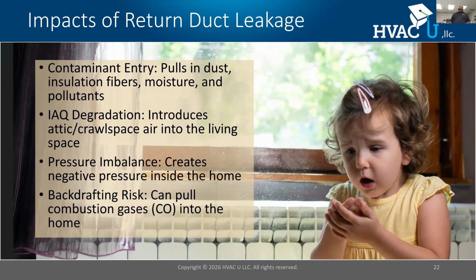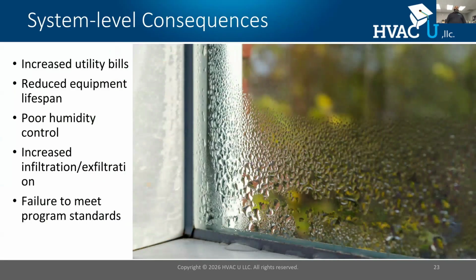All right, so if we have air leak on the return side, we have the same problems and it can cause some IAQ issues. In addition to that, we can also trigger our building shell related problems and even have problems with our combustion appliances. Okay. What about system wide consequences? How does a lack of airflow help that?